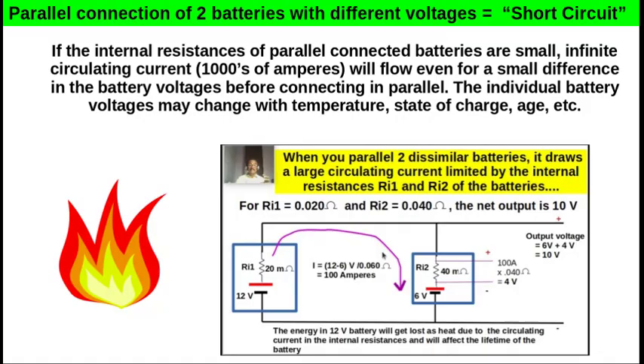Parallel connection of two batteries with different voltages is equivalent to a short circuit. Thousands of amperes can flow, and the current is simply limited by the internal resistances of the battery. In this example, I am showing the current is around 100 amperes, but if the internal resistances are small, the current will be very high. It can be up to thousands of amperes.